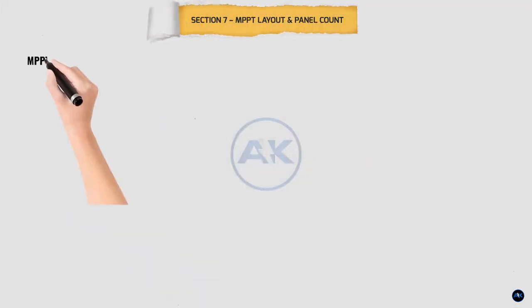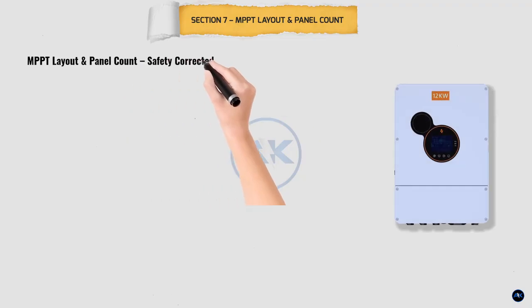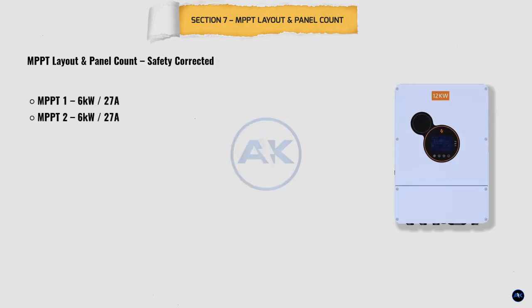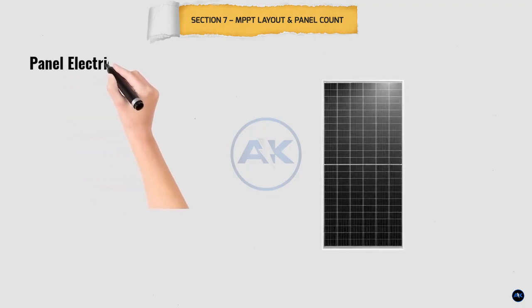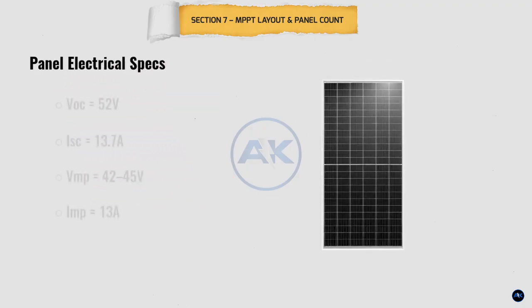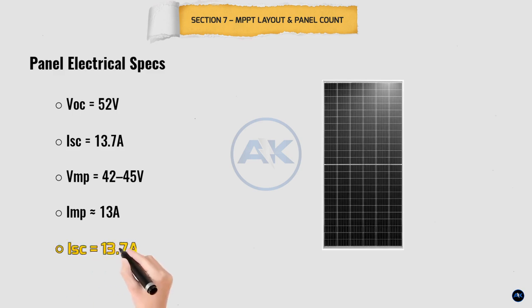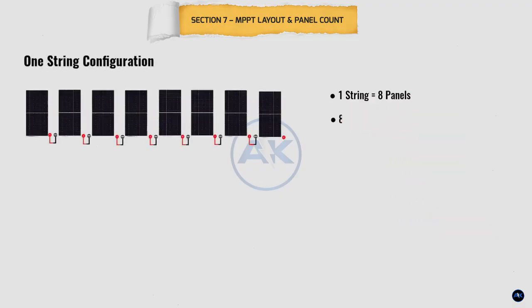Now that we've confirmed our string voltage is safe, let's design the MPPT layout with actual panel specifications. Each 580-watt panel has open circuit voltage of 52 volts, short circuit current of 13.7 amps, and max power current of 13 amps. For safety, we always use short circuit current for MPPT calculations. Let's calculate one string first. 8 panels times 580 watts equals 4,640 watts, or 4.64 kilowatts.